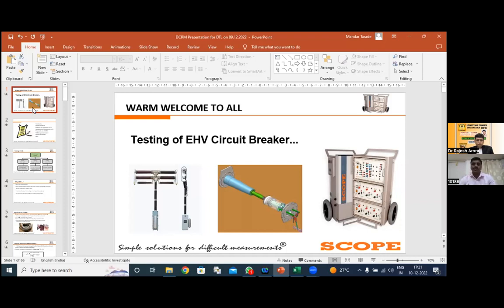The operation of the circuit breaker is divided into two categories. First is manual and second is automatic. In the manual case, wherever we want to perform diagnostics or health assessment of the different duties available in the substation or switchyard, we isolate the circuits with the help of the circuit breaker. In the automatic type, with the help of the relay we assess the fault condition, depending on the algorithm in the relay, and if a fault is there, we stop that fault in the entire substation with the help of the circuit breaker. The relay immediately triggers the circuit breaker, and accordingly the circuit breaker will trip. So these are the two operation mediums of the circuit breaker.